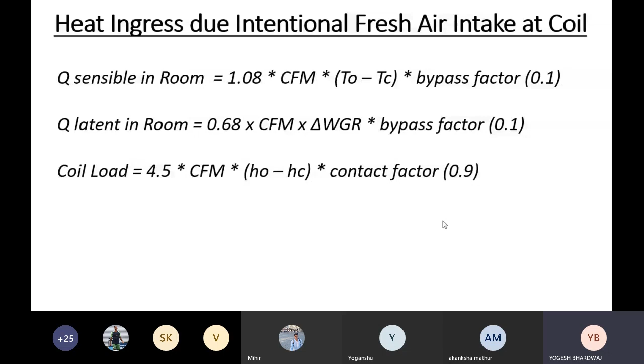For the 10% air which actually bypasses my cooling coil, I am evaluating it in my room heat load. So for that 10% air, I will calculate the heat load separately as Q sensible and Q latent, because I need to calculate my sensible heat factor. The air which is coming directly on the coil, the load because of that is not considered in the sensible heat ratio. That's why we calculate the coil load separately. So here, when you have calculated all of the heat transmission through the exterior components and interior components, and then the coil load, then you can calculate the sensible heat ratio.